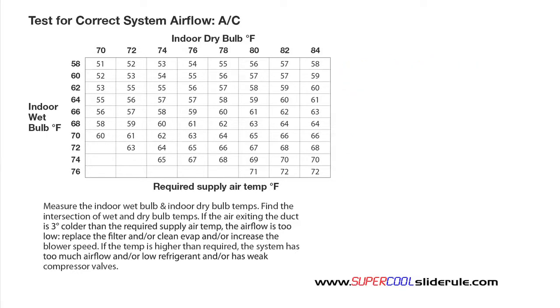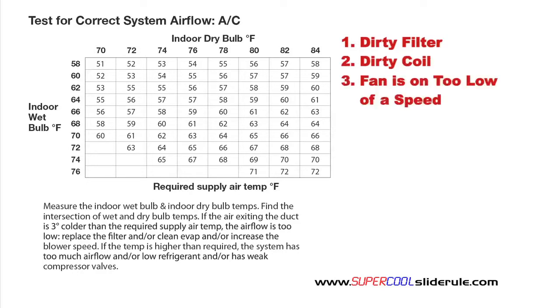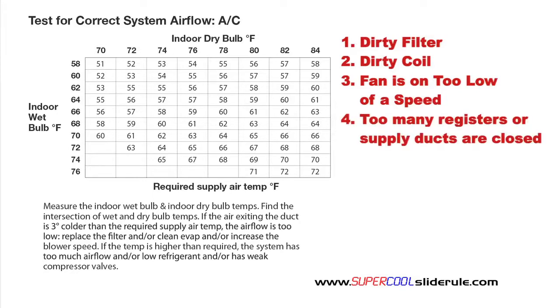Now if the measured temperature is more than 3 degrees colder than this, the most common problems are: one, a dirty filter; two, a dirty coil; three, the fan is on too low of its speed — move the fan control to a higher speed; four, too many registers or supply ducts are closed — go open those; five, the duct system is too small for the system.